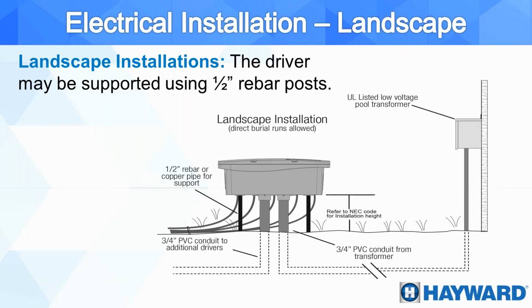And now here we take a look at the installation options on how we would install this driver. The driver installation recommendations is the same as we saw for the transformer earlier, or the same as what we saw for the junction boxes, I'm sorry. So the driver is designed to be installed outside. It can rain on it. It can get the sun. That is not an issue. We are going to install it the same way. It is going to be elevated, so it is not going to be directly on the ground. So we elevate it about 8 inches, and we can also use a rebar that goes here on the side in order to support the driver.